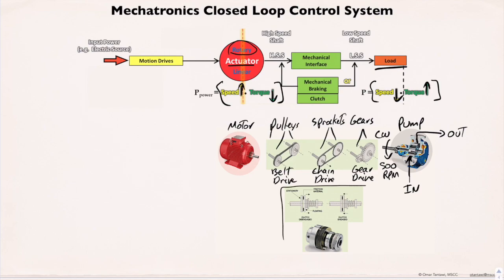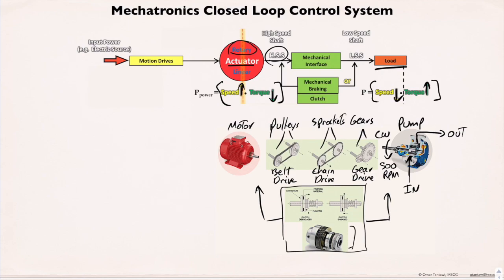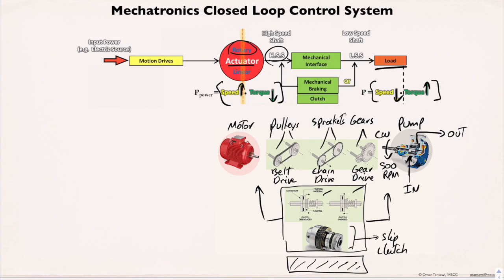A mechanical clutch is used as a protection device in case of an overload and can be placed on either side — the pump shaft or the motor shaft — commonly on the high-speed shaft. The device shown is called a slip clutch, and there are two methods of operation: engagement and disengagement. A mechanical brake is used for safety, either as a separate device or a built-in mechanism to lock the pump in position from reversing.